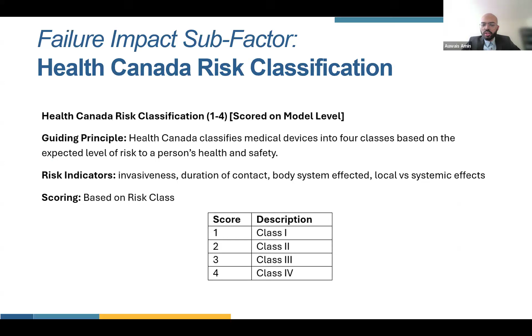Another thing I did, in order to remove subjectivity for the physical risk factor, was switch it with another thing that we track in our CMMS, which is the Health Canada risk classification, as a proxy to this physical risk that a medical device might have. And it was a direct mapping between the 4 classes in my calculation.